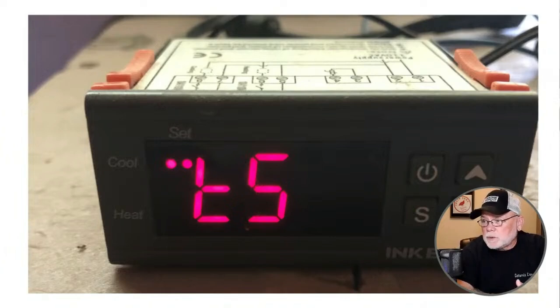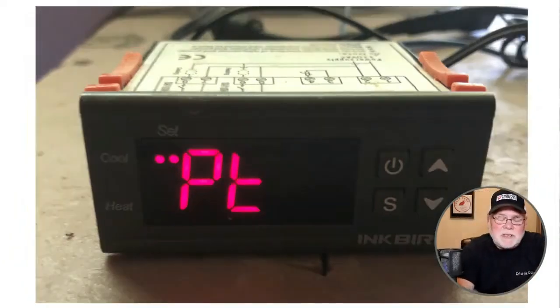You can see on this shot here, it's TS, which stands for temperature set. And this is actually the first setting that comes up when you go into the settings. And it needs to be set to 99 degrees. Like I said in the last shot, some people do 100, but I do 99. The second setting is PT, which I have no idea what PT stands for, but that is your compressor delay. And the compressor delay, you want the value set to 0. By default, I think it's 3.